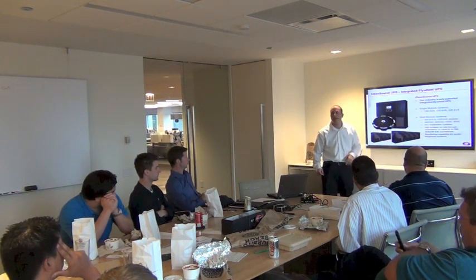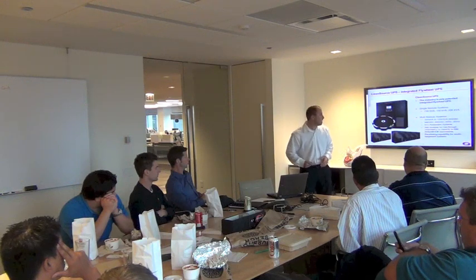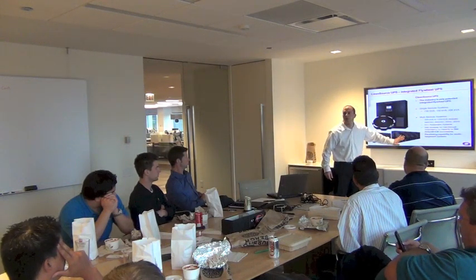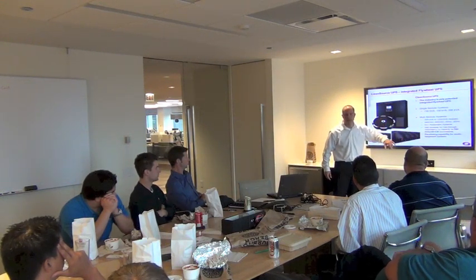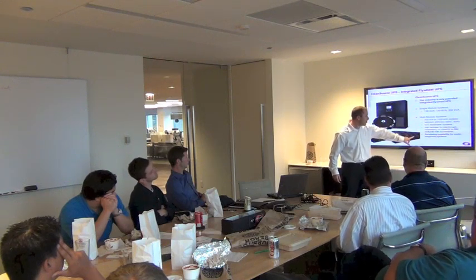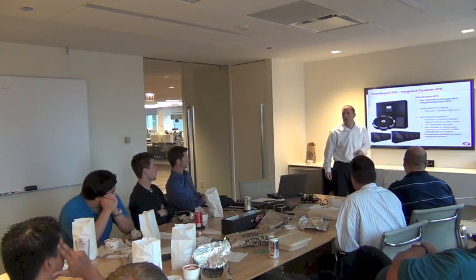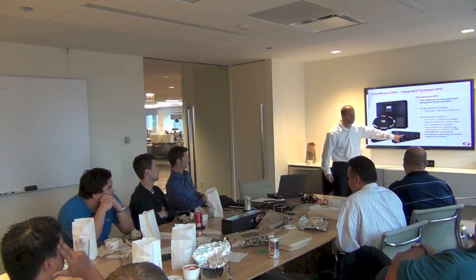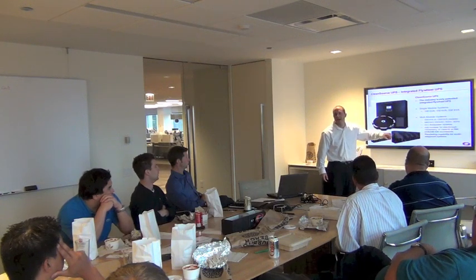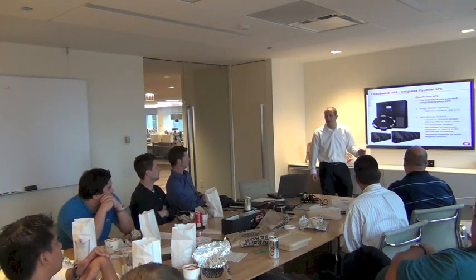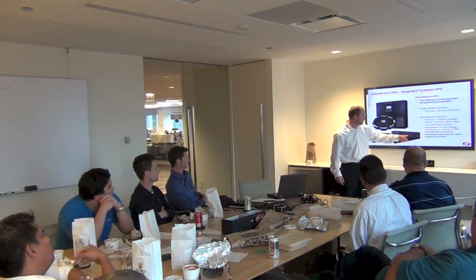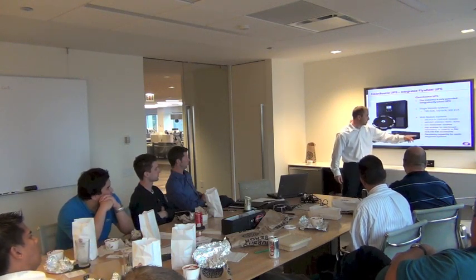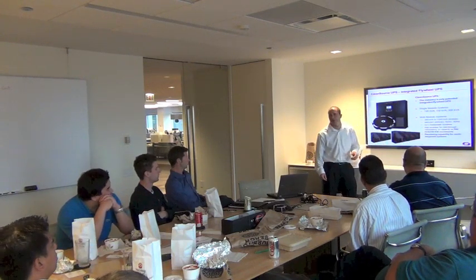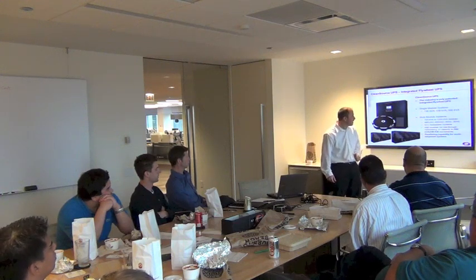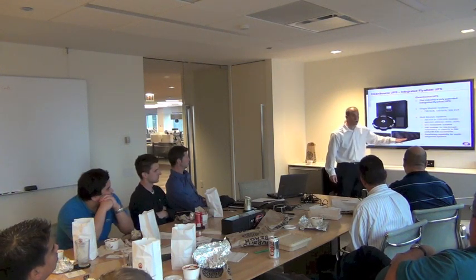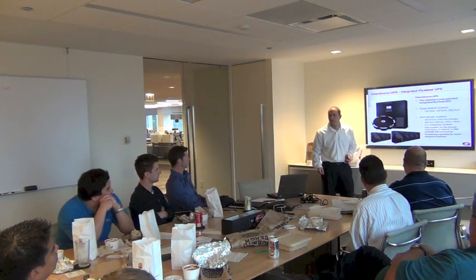Each systems cabinet is not a control cabinet; it's basically just a slave to the rest of the UPS. All the critical components and all the brains are distributed in each one of these 300 kVA cabinets. So this cabinet is basically just tying them together. Inside the systems cabinet, you have an isolation disconnect switch for each flywheel cabinet. If you want to do maintenance on one and leave the other 2 units online, you can isolate it via the isolation disconnect switches. So this would be like a 900 kVA UPS or a 600 N+1.